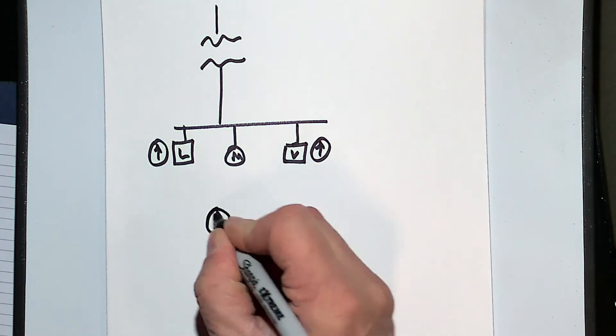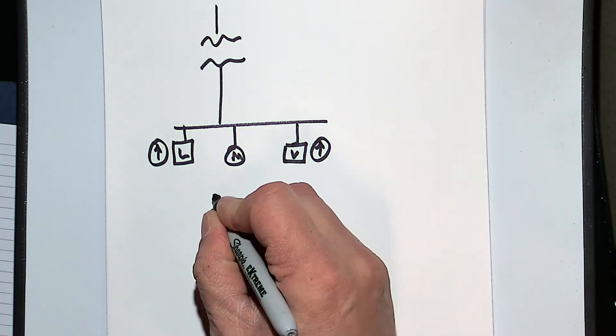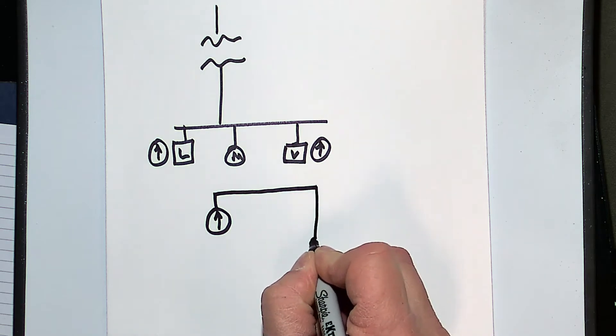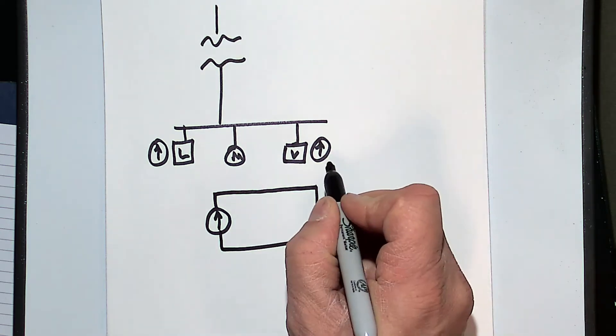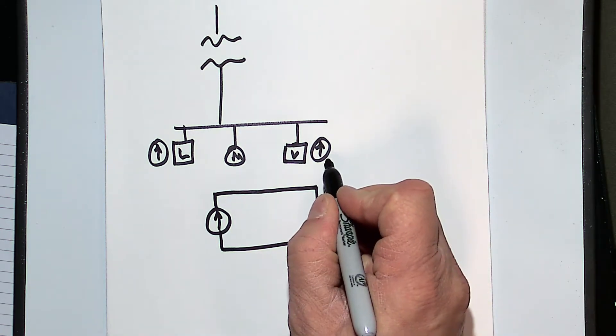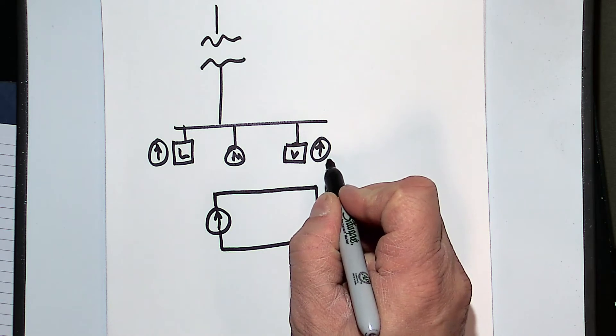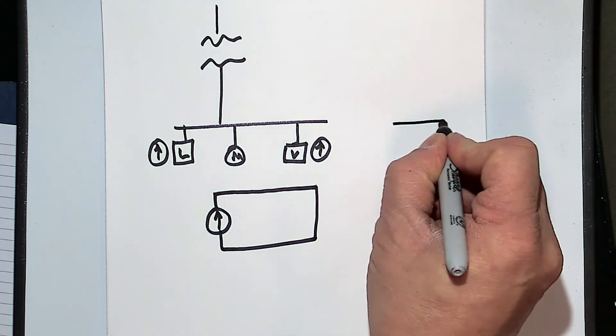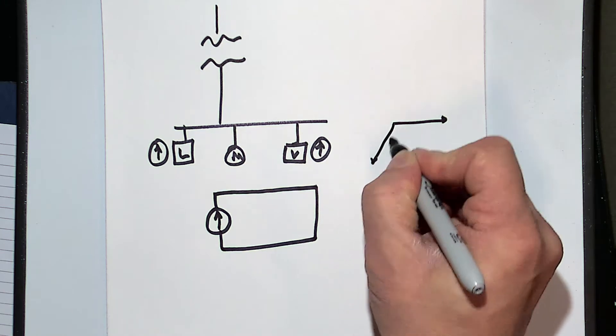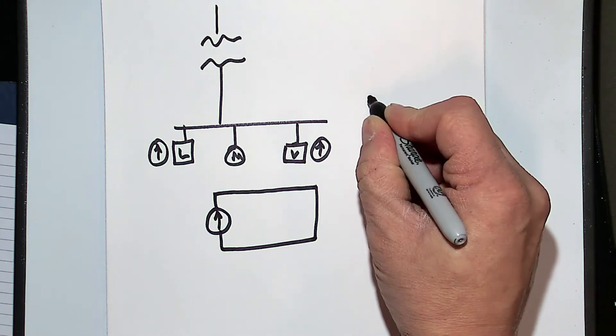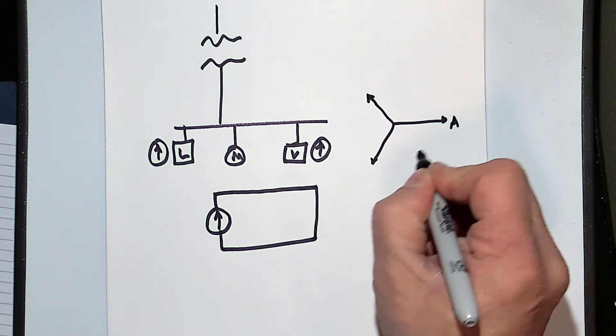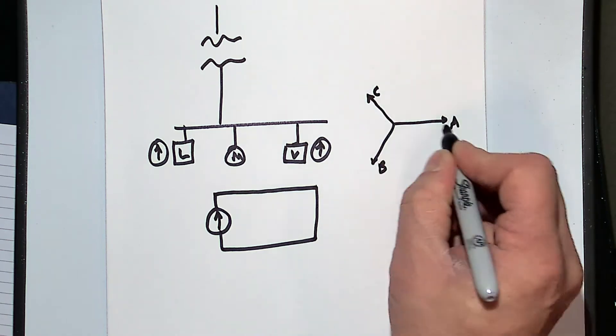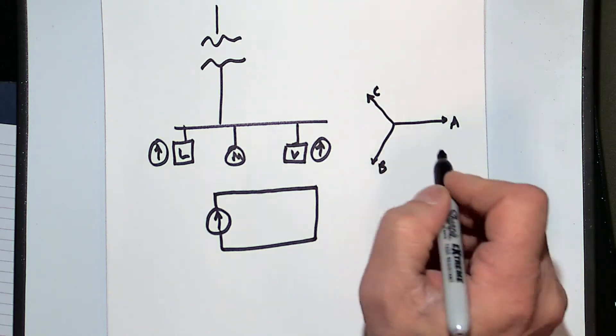What happens is, current by its nature has to flow in a loop. It has to go out and come back. A lot of people think that harmonic currents go out on the phases and back on ground, but they don't. They go out on phase A and come back on B and C. And they go out on B and go back on A and C, and so forth.